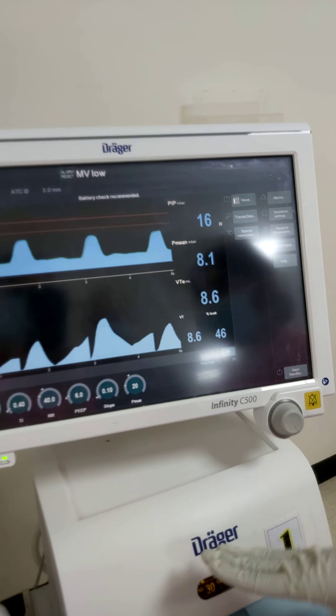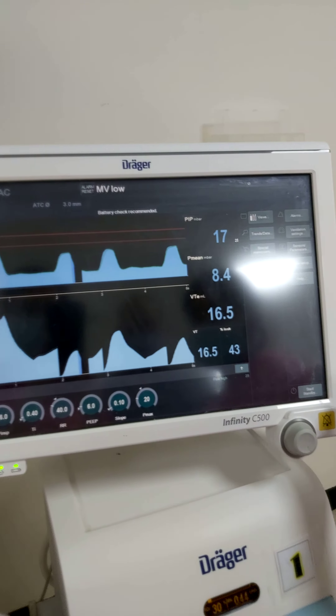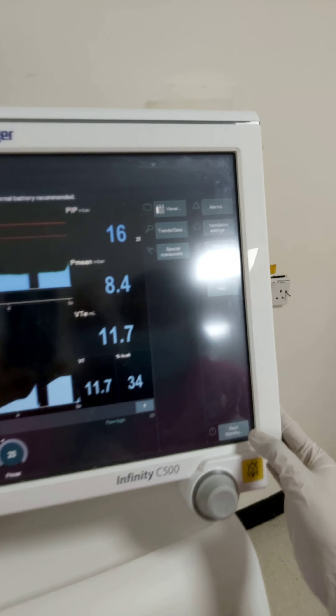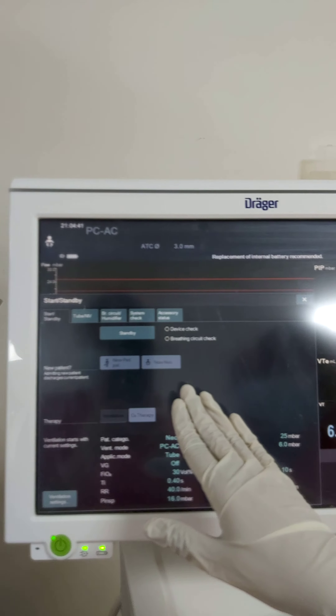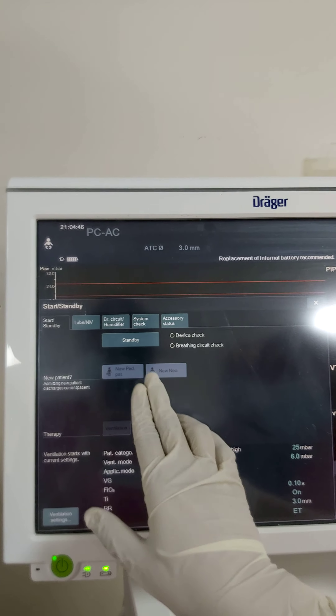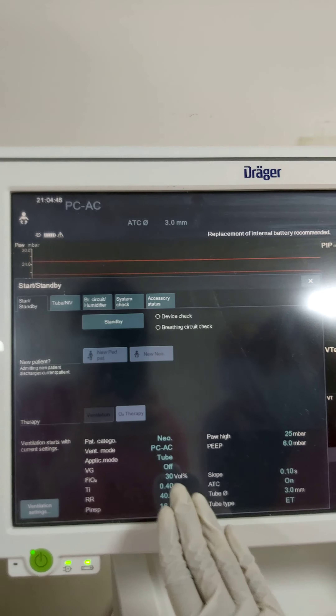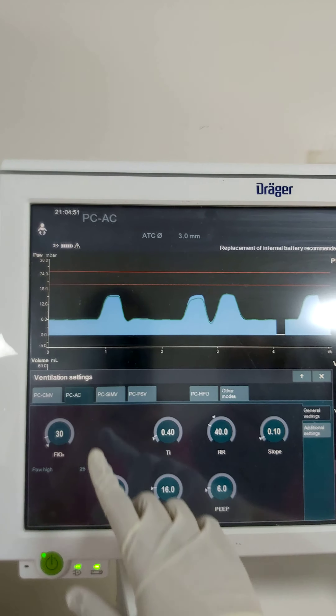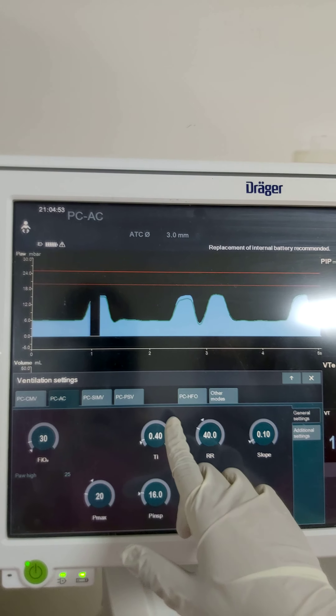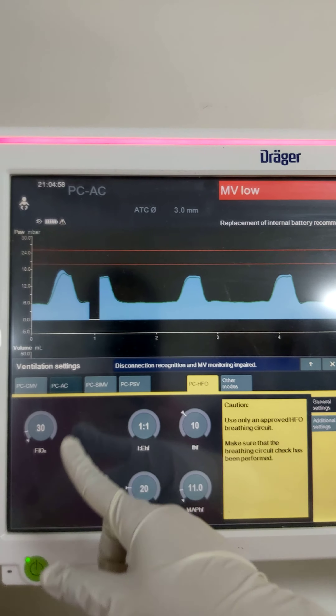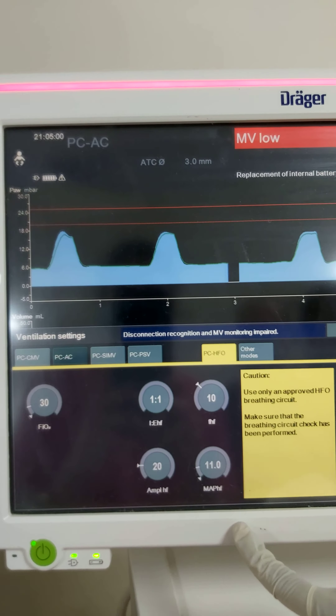So how do we shift the baby from conventional to high frequency? This is the conventional mode. From here we go to stand-by. The parameters are already set because the baby was previously on conventional mode. We press the ventilation settings, where we can see the parameters. There is also a high frequency option — we just press here to access the high frequency settings.